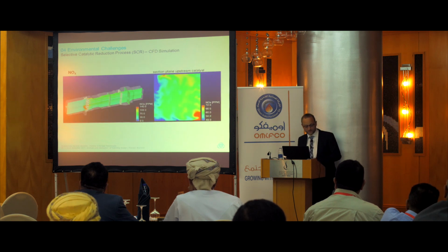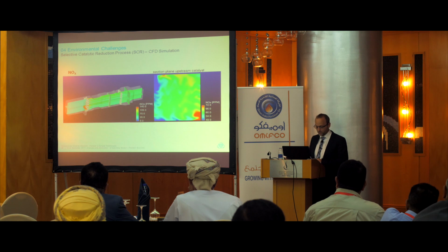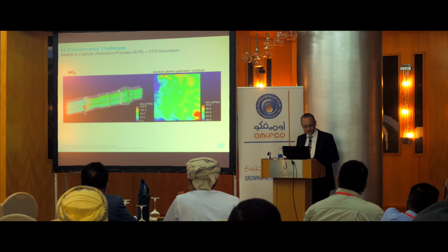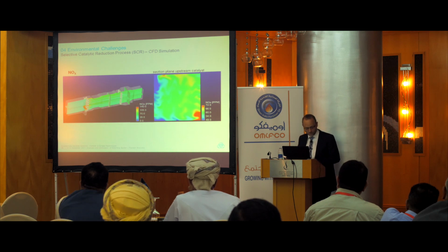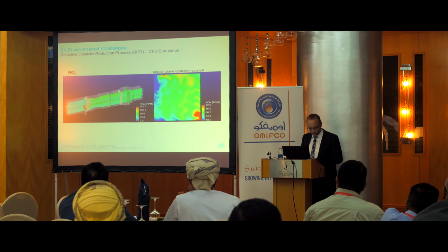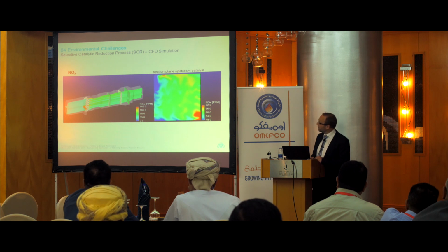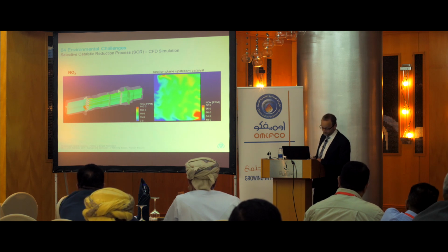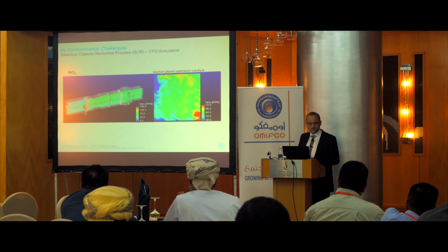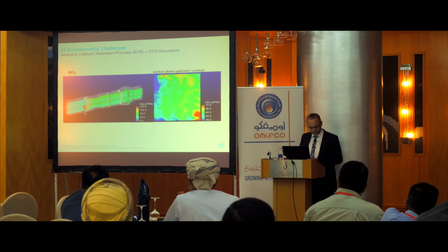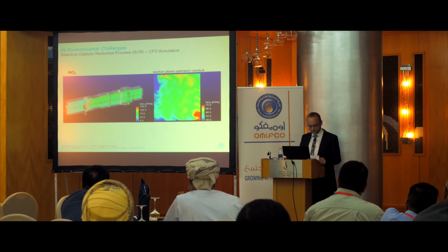Of course, for every SCR unit, a CFD analysis will be prepared in order to optimize the flow in front of the catalyst. And especially, we need to ensure a correct NOx to ammonia relation at any section of the inlet plane. Otherwise, both the NOx emissions and the ammonia slip at the stack will increase.